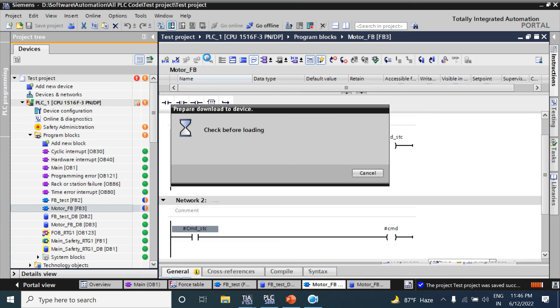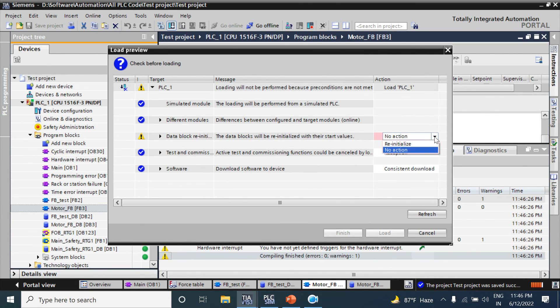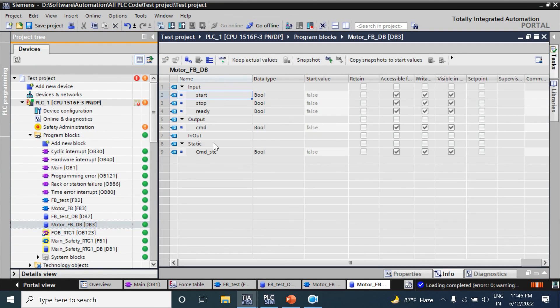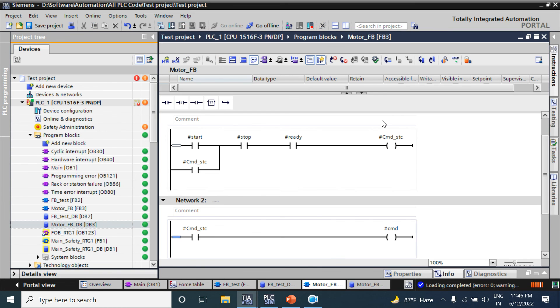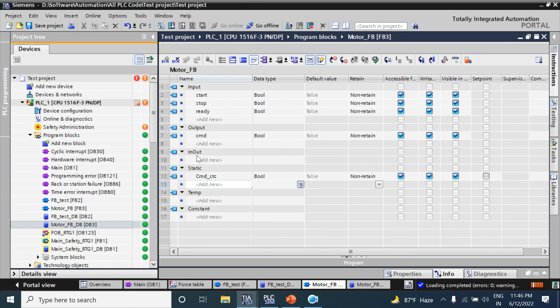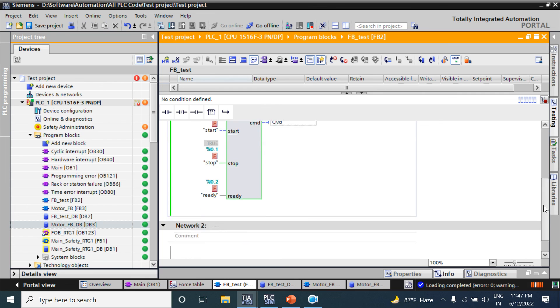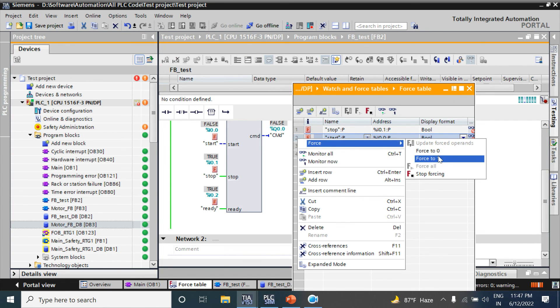After changing the Motor FB there is a re-initialize call prompt. In Motor FB the static tag is visible. In an FB library block, Input, Output, InOut, and Static parameters all get created in the instance DB block - not Temporary or Constant. Checking again - it is now false. I am giving a Start command and the Command is true.